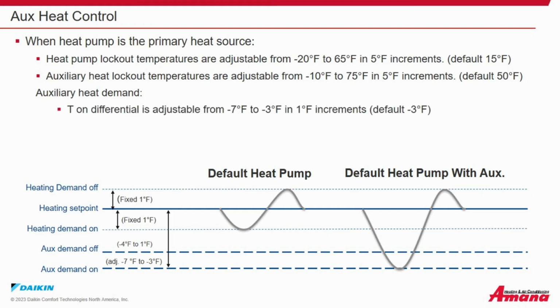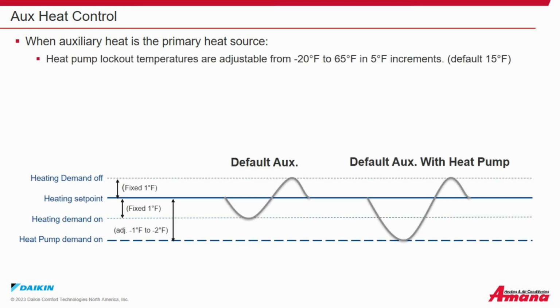T-on differential is adjustable from -7 to -3 degrees Fahrenheit in 1 degree increments. Default -3. T-off differential is adjustable from -4 degrees to 1 degree Fahrenheit in 1 degree increments. Default is 1 degree. When auxiliary heat is the primary heat source, the heat pump lockout temperatures are adjustable from -20 degrees to 65 degrees Fahrenheit in 5 degree increments. Default is 15 degrees. Set point differential can be set at -9, -7, -4, and -2 degrees Fahrenheit.